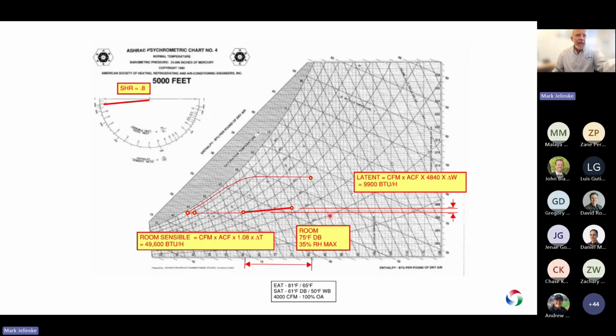Well, perhaps to keep within below 35% relative humidity at 75 degrees - here's 10, 20, 30, 35%. Could have done that with 46 degree air, but the other thing is that in order to meet this delta H of cooling, we would have had to have less supply air. Instead of 4,000 CFM, that's about double the delta T there.